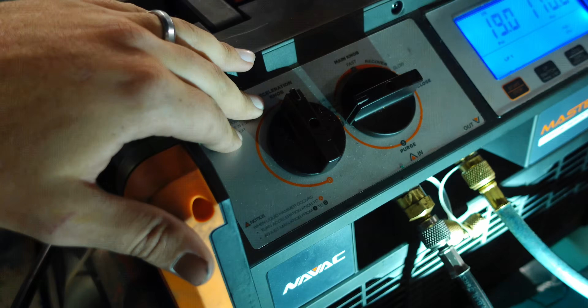So when you're in the A setting, you're running through both of those pumps parallel, and it's just a constant pass-through feed. Per their engineering theory, switching to the B setting changes the valving internally on the pump, making it to where pump 1 runs in series through pump 2, and it does a stage pumping instead. Now, the mistake I was making was thinking of it in pure terms of vapor, but their actual purpose and goal is to help when you have very low volume left in the system. So when you start to get real low on your pressure, that means you have very low refrigerant volume.